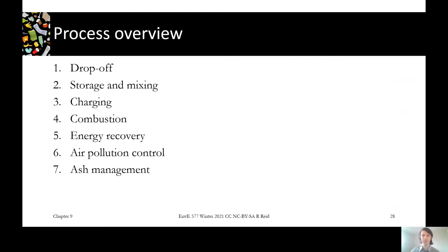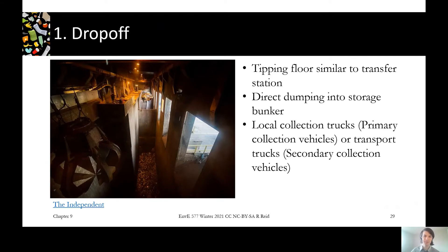Stepping through the previous video, you would have seen all these steps: waste comes in and is dropped off into a big bunker, stored and mixed, then loaded into the combustion chamber. There's the actual combustion reaction, energy recovery with the hot flue gases, then all the flue gases pass through air pollution control. All the ash from air pollution control, as well as the bottom ash from the combustion chamber, are managed through ash management systems. So what does each of those look like?